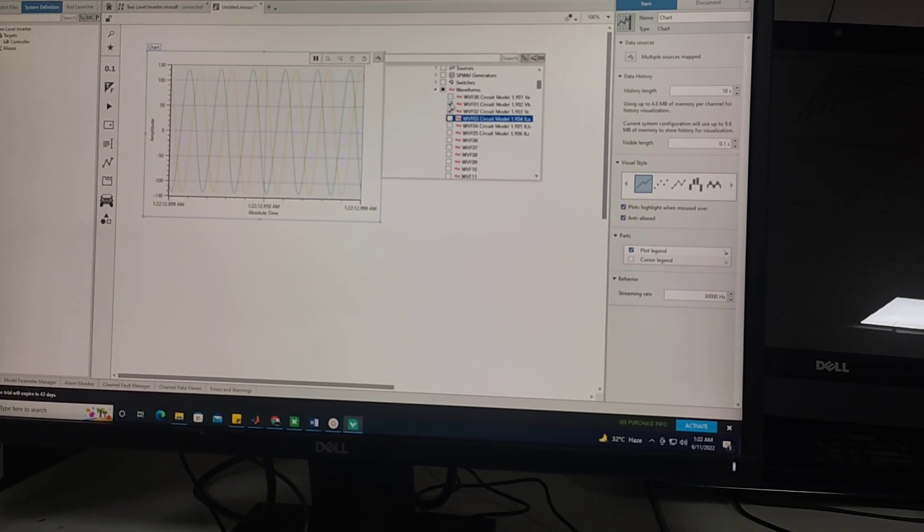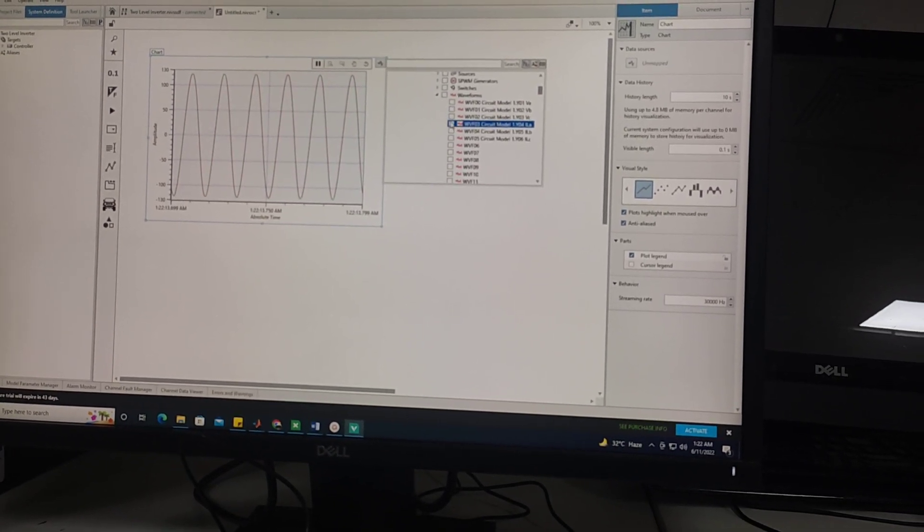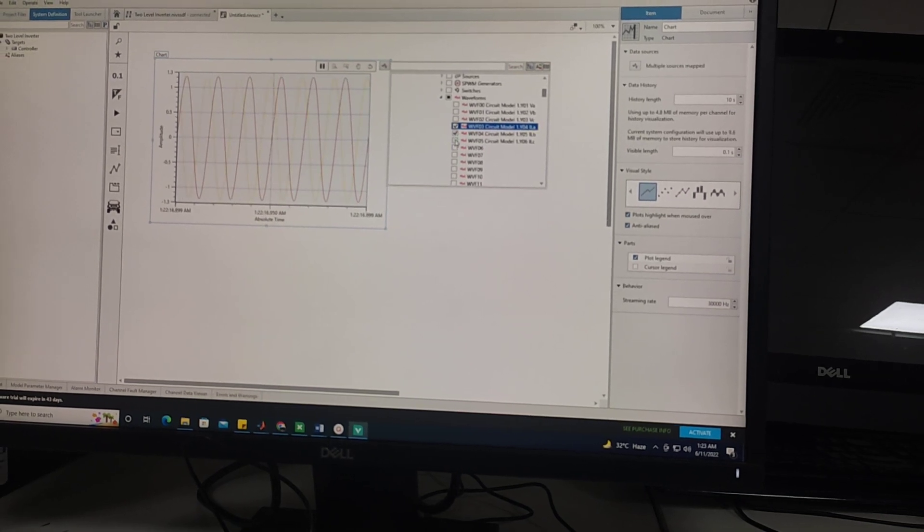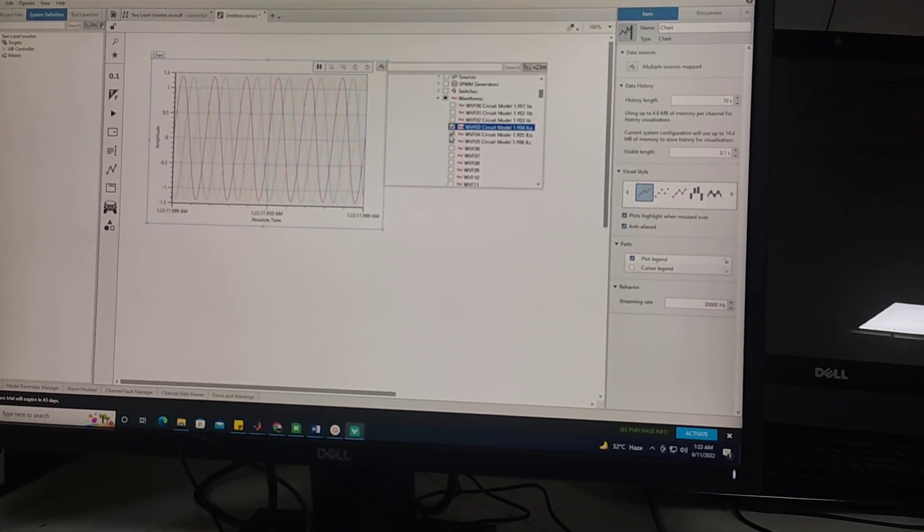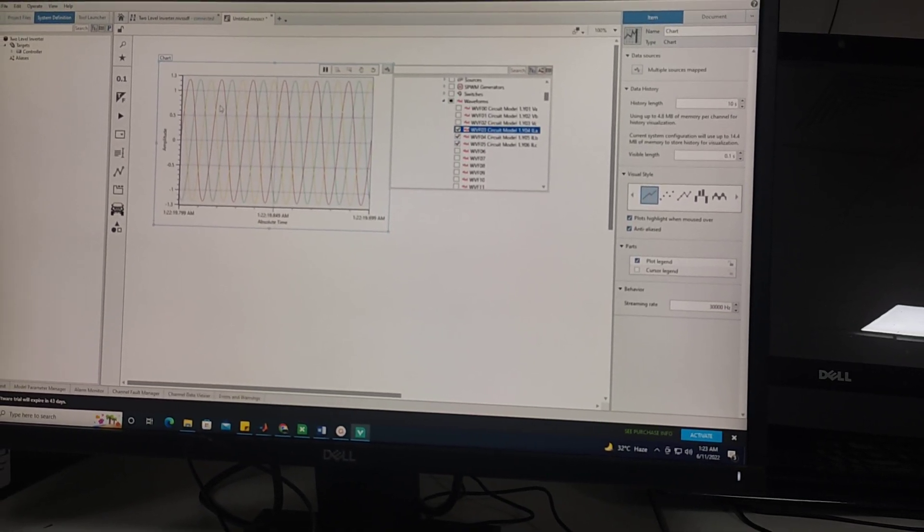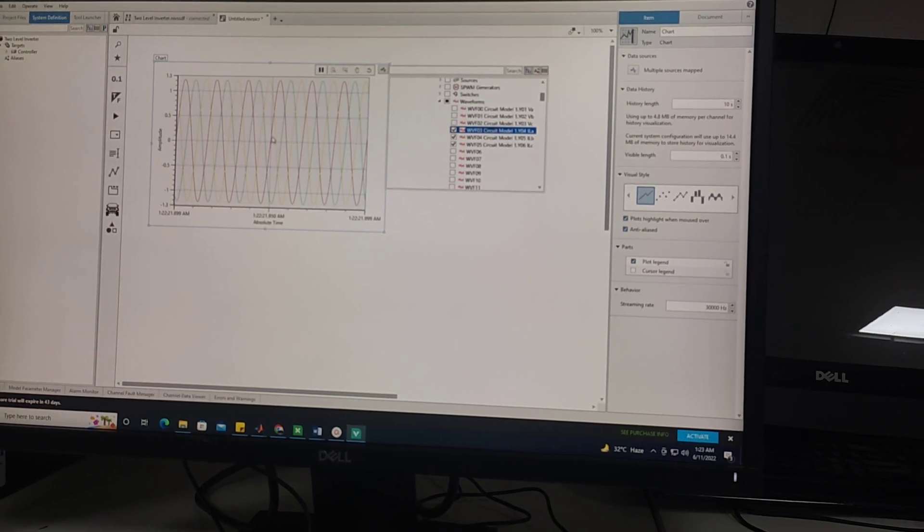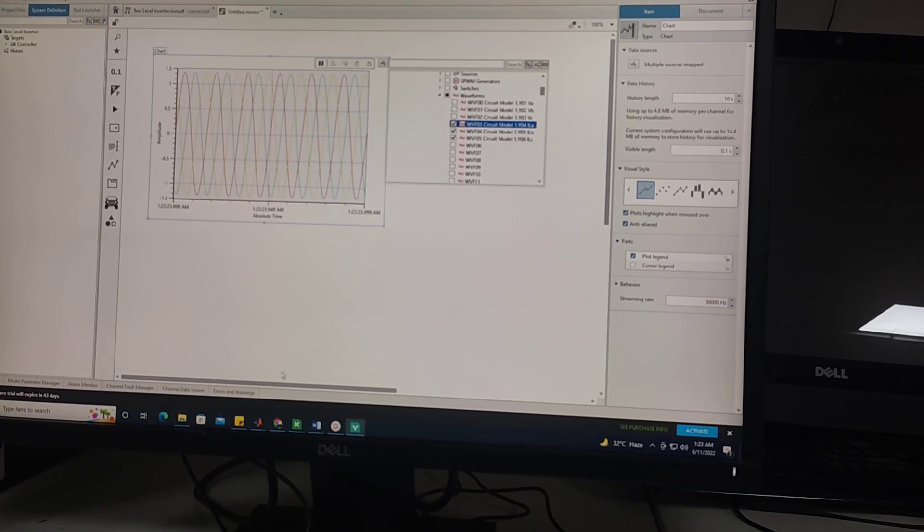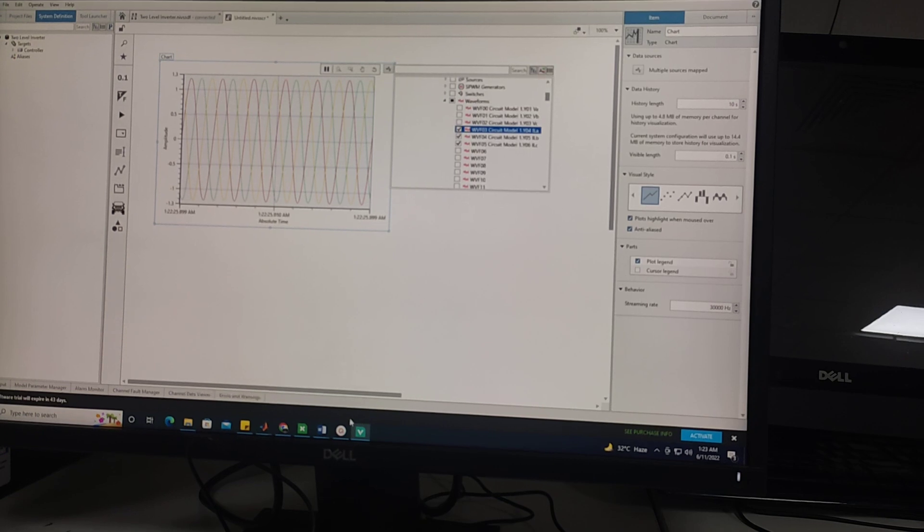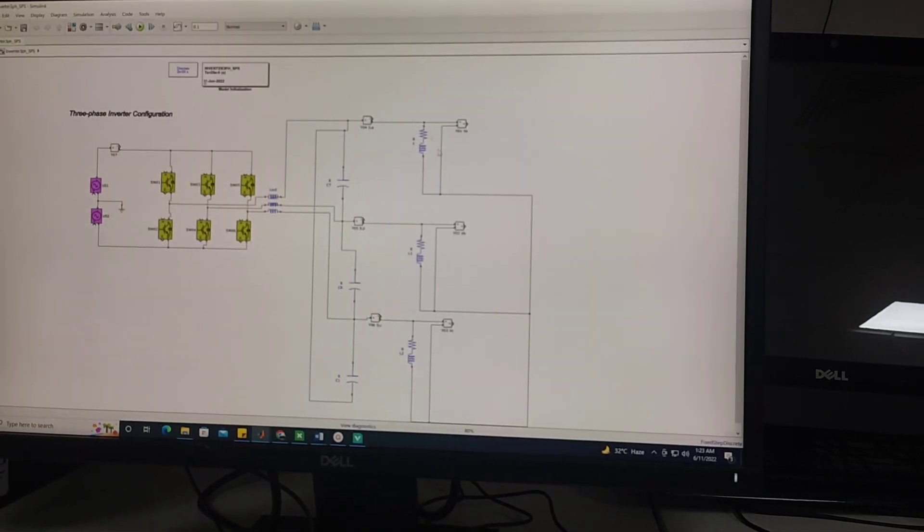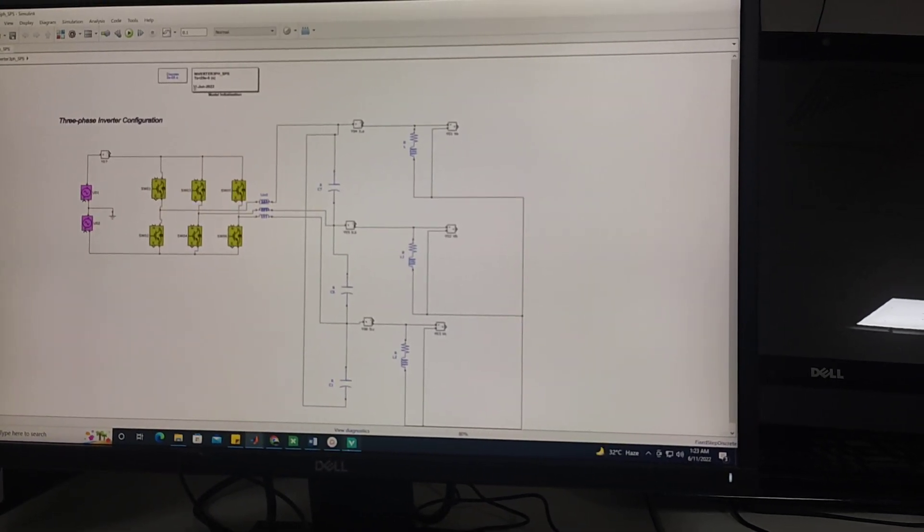And then these are the results for my output current. Current is purely sinusoidal because passive filter is installed and it is working satisfactorily.